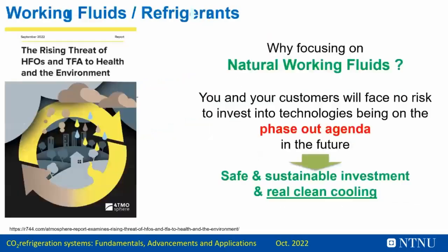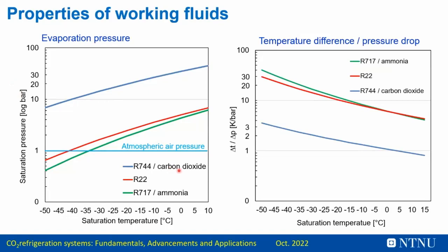So when we look at the properties of the working fluids, focusing a little bit on CO2, R22, which you are very familiar with, and just as a reference also ammonia, we can see that the saturation pressure at different saturation temperatures is much higher for CO2 compared to R22 or ammonia. This is significantly higher, which has its benefits because, as I will show later, the pressure ratios are lower and the density of the fluid is higher, so we can have much smaller pipes compared to other fluids. When it comes to the temperature difference at the given pressure drop, we see also the opposite, that the value for 1 Kelvin, for 1 bar pressure difference, the delta T in ammonia or R22 are quite high at these very low temperatures.